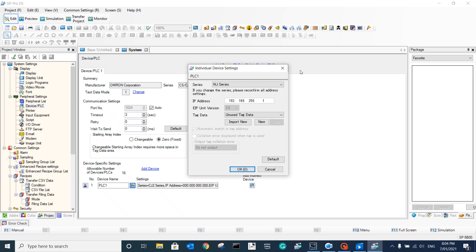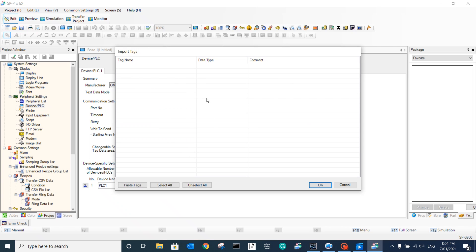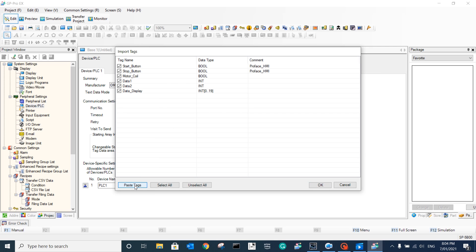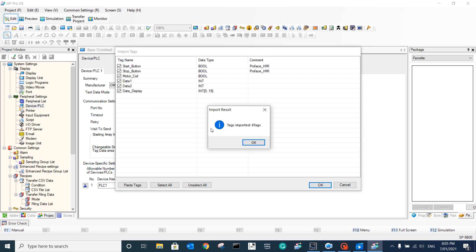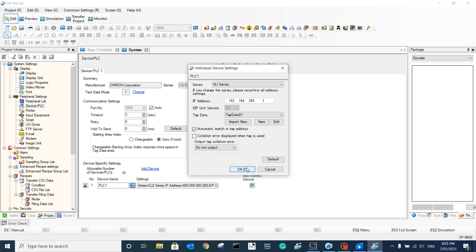Then we come here to import the variables. Because we already set up and published all of the data and exported to the CX designer - it was just copied to the clipboard - from here you can easily paste all of the text. See how simple that is? By doing this, you can easily import all of these tags to the Pro-face HMI. Then we click OK. You can see we have already imported six tags.